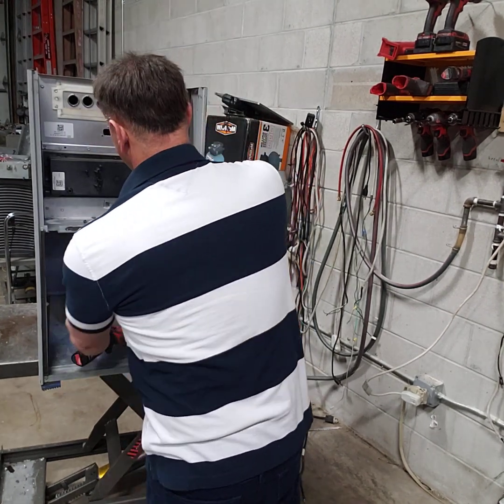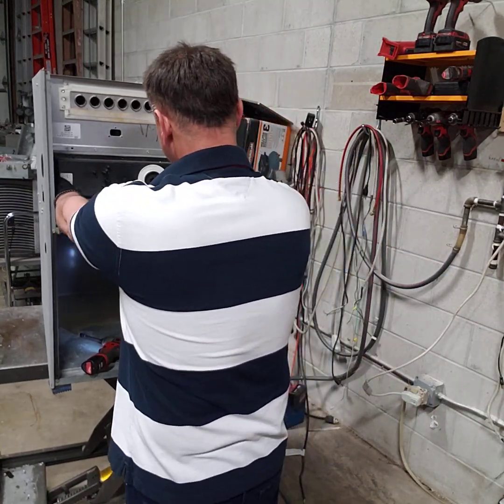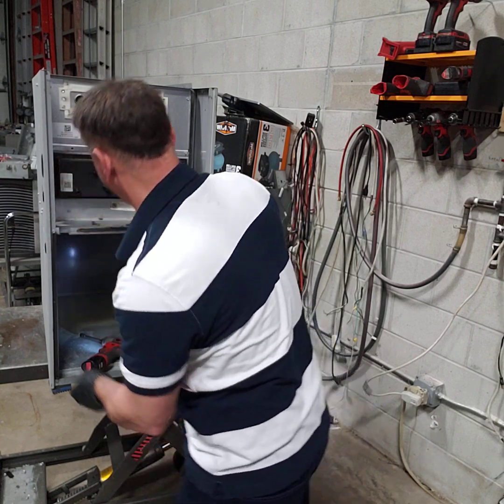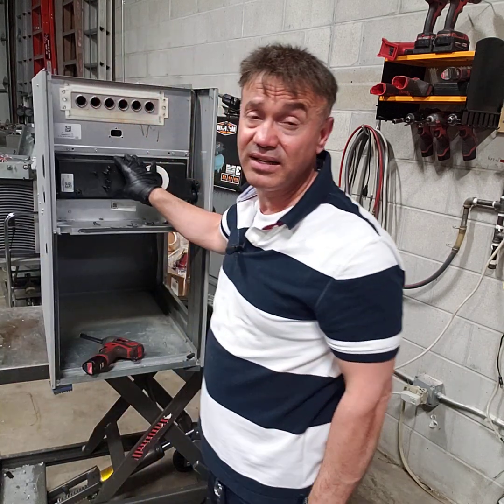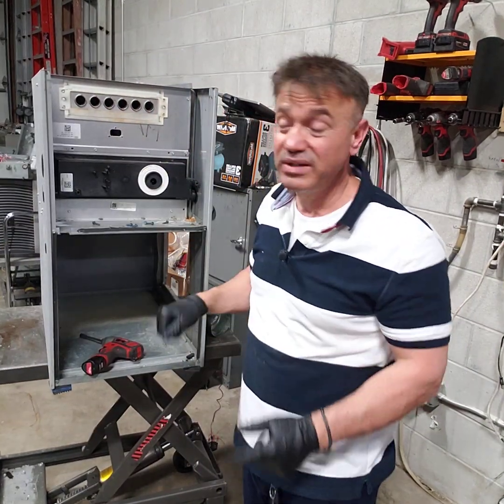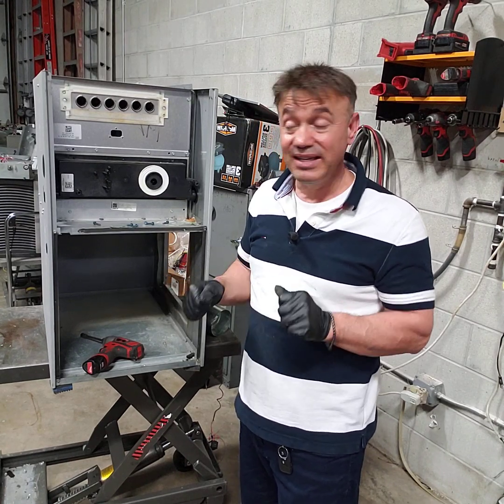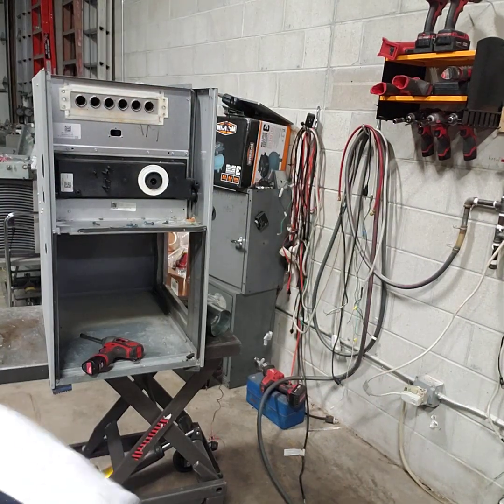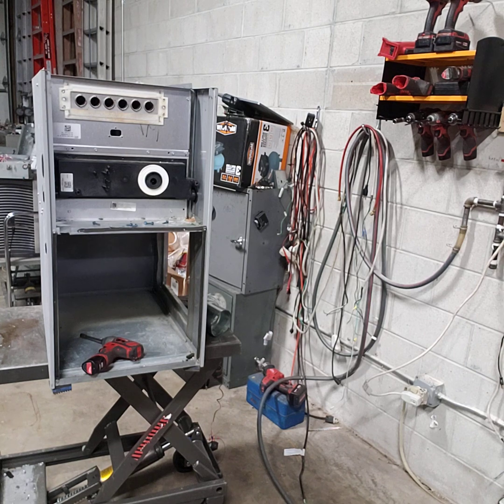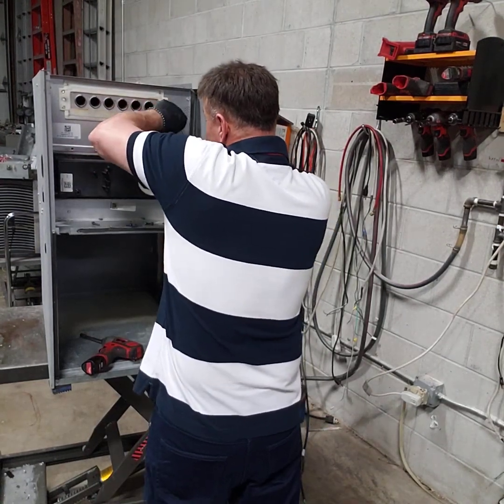Basically, this furnace, I don't have enough time to go through it, but it has a problem with the blower. So it's either the blower was bad or the heat exchanger. That's the other thing I want to tell you about why a lot of technicians don't want to go through this. Putting in a heat exchanger has to be perfectly done. If any place is leaking, there's carbon monoxide leaks, they can be in big trouble. That's why a lot of people say, we'll give you an estimate for a brand new one. I'm sorry, we're not gonna replace your heat exchanger because of the liability.